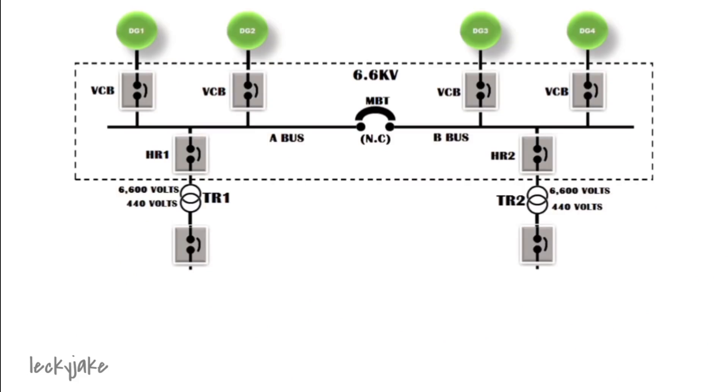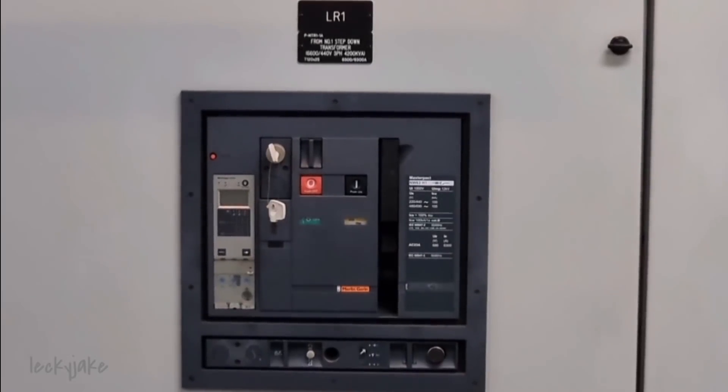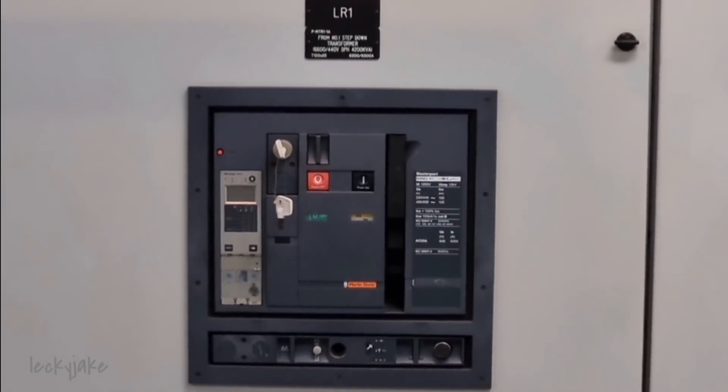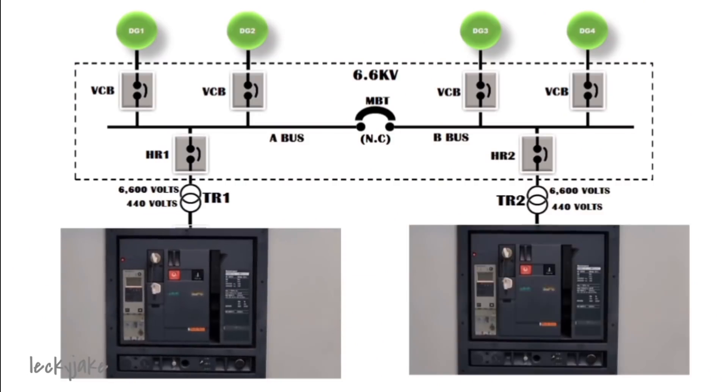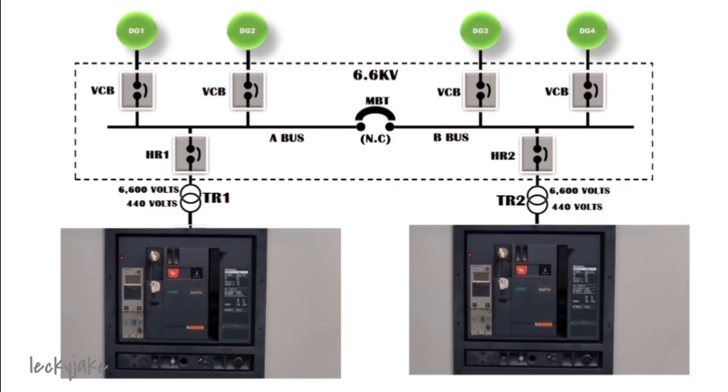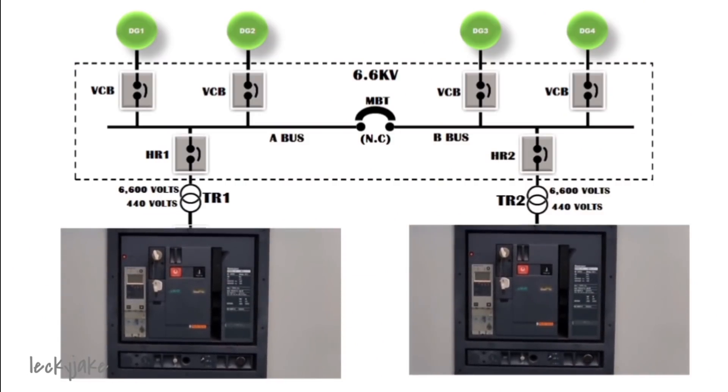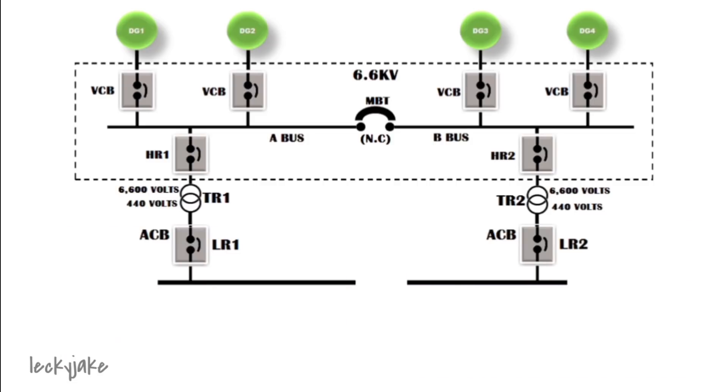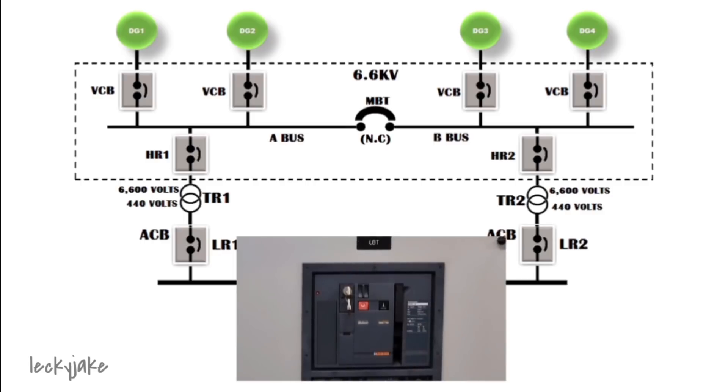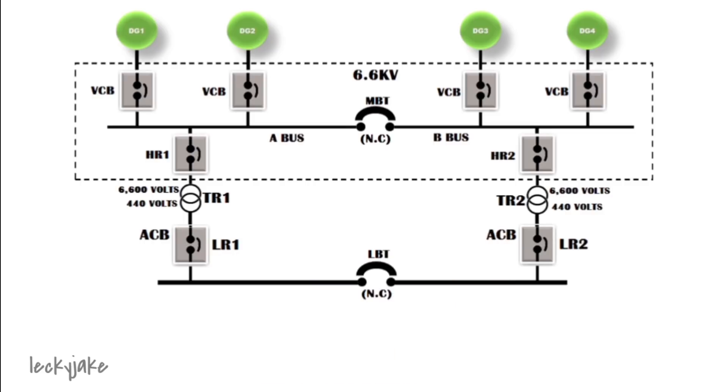Since the primary is 6600 and the secondary will be 440 volts, this will pass then to a breaker which is an ACB or an air circuit breaker. Again, this is a Korean built vessel so they are using LR for tagging of the low voltage breaker. It is the same setup with the 6600 volts, they are also having this low voltage bus tie. These two air circuit breakers are mechanically interlocked to ensure that only one transformer can feed the 440 section at any time.